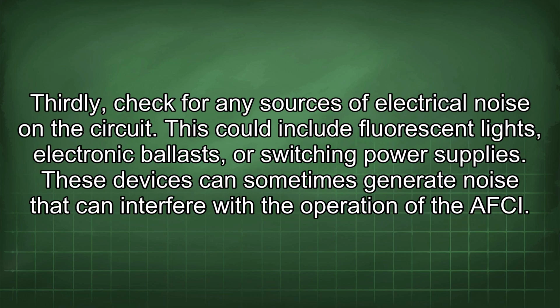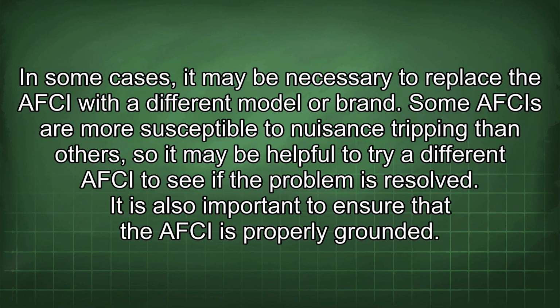Thirdly, check for any sources of electrical noise in the circuit. This could include fluorescent lights, electronic ballasts, or switching power supplies. These devices can sometimes generate noise that can interfere with the operation of the AFCI. In some cases, it may be necessary to replace the AFCI with a different model or brand. Some AFCIs are more susceptible to nuisance tripping than others, so it may be helpful to try a different AFCI to see if the problem is resolved.